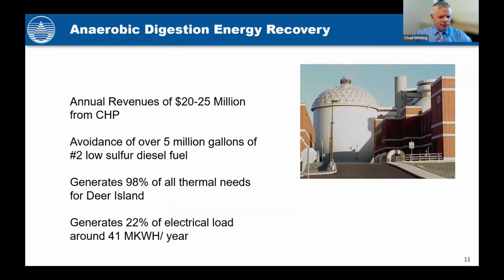So some of our energy benefits with our CHP from anaerobic digestion, we generate annual revenues between 20 and 25 million from our CHP process. We're about 60% off the grid. About 78% of that 60 is the digester gas. We avoid the consumption of over 5 million gallons of number 2 low sulfur diesel fuel to meet the thermal needs of Deer Island. We generate 98% of our thermal needs for all of Deer Island and the digesters. So we supplement in the wintertime slightly with a little bit of fuel oil, as the digester gas is not enough to keep our temperatures up in the colder months.